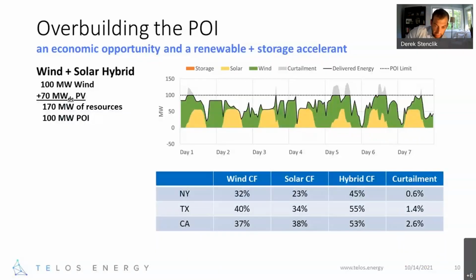So a couple of quick points. I did say interconnection was one of the most, if not the most, valuable aspects of a hybrid. We did some back of the envelope math. If you looked at 3 locations - New York, Texas, California - and played around with different configurations of wind and solar. Here we took an example: a 100 megawatt point of interconnect, with a 100 megawatt wind plant, and you wanted to add 70 megawatts of PV. We did that across 3 different locations, and you can really bump up the capacity factor of that 100 megawatt POI, cranking up capacity factors with very little curtailment.